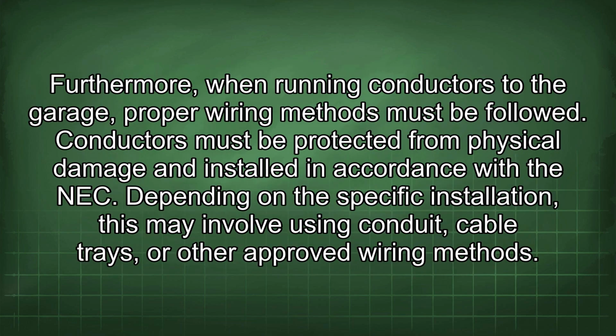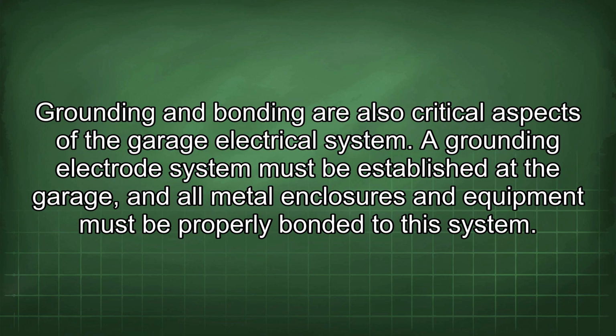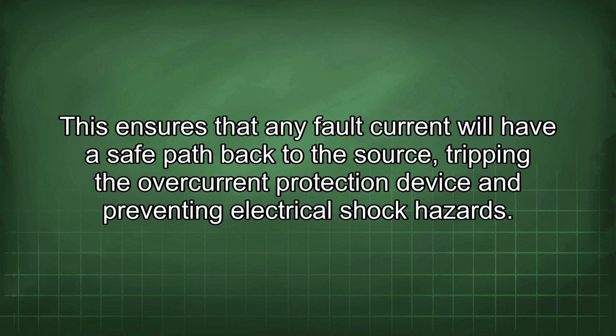Furthermore, when running conductors to the garage, proper wiring methods must be followed. Conductors must be protected from physical damage and installed in accordance with the NEC. Depending on the specific installation, this may involve using conduit, cable trays, or other approved wiring methods. Grounding and bonding are also critical aspects of the garage electrical system. A grounding electrode system must be established at the garage, and all metal enclosures and equipment must be properly bonded to the system. This ensures that any fault current will have a safe path back to the source, tripping the overcurrent protection device and preventing electrical shock hazards.